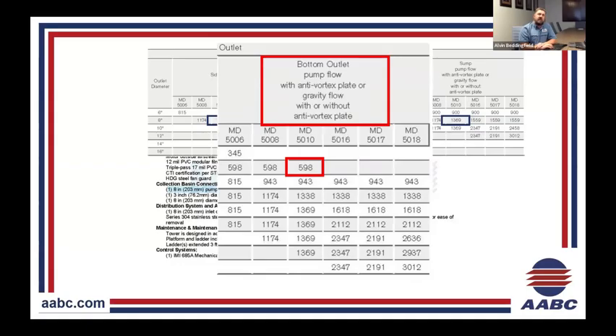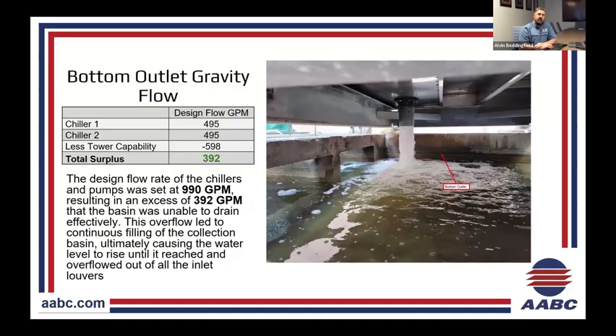That wasn't what it was, but it was gravity flow with or without the vortex plate. Either one can produce the same amount of GPM. So 598. Okay, well, we know now that we're really short of what that tower can actually drain naturally out of the cooling tower. So a snapshot of underneath the tower when we're having that scenario. So obviously chiller 1 and chiller 2, roughing them down back into design GPM to retest this system to try to figure out why we're overflowing and do we have too much.